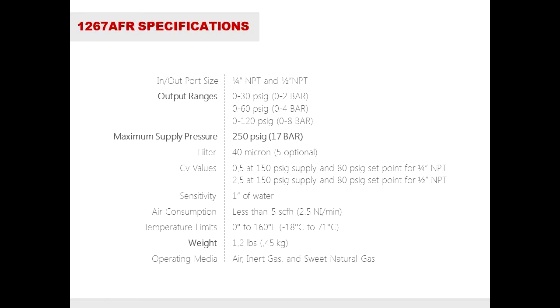The maximum supply pressure is 250 PSI. This is the maximum pressure that can enter the air filter regulator without damaging or failure occurring to the diaphragm and the air filter regulator itself.